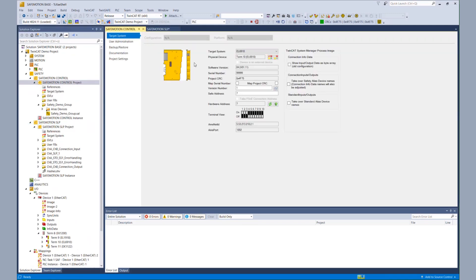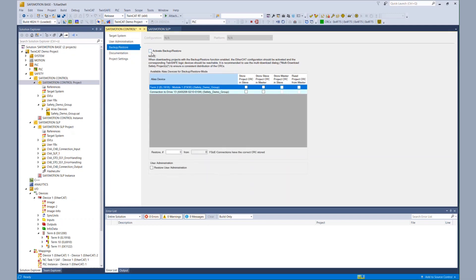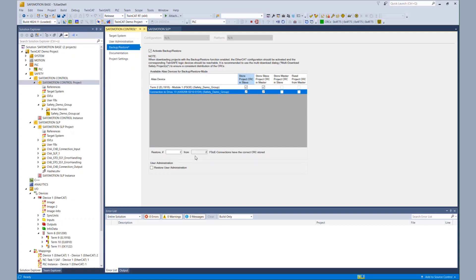On the other side, the EL6910 — we go to the target system and backup and restore properties and activate the backup and restore. For the EL6910 it's a little bit different because we have two connections: the EL1918 and the connection to the AX8000. In this case, we want to store our project CRC in the slave, and we want to store the slave project CRC in the master. Below we can configure how many yellow terminals should answer correctly. Here we say we want to restore if both connections are answering with the correct CRC, but I can also configure that only one has to answer correctly.